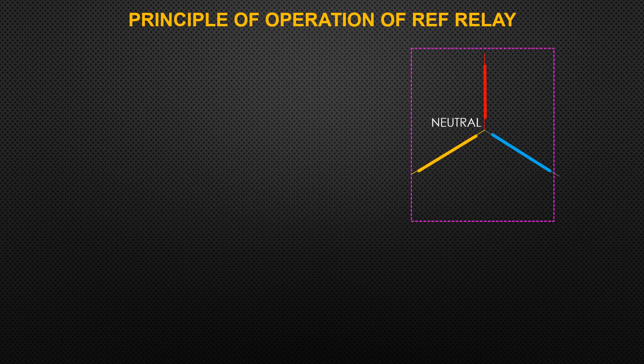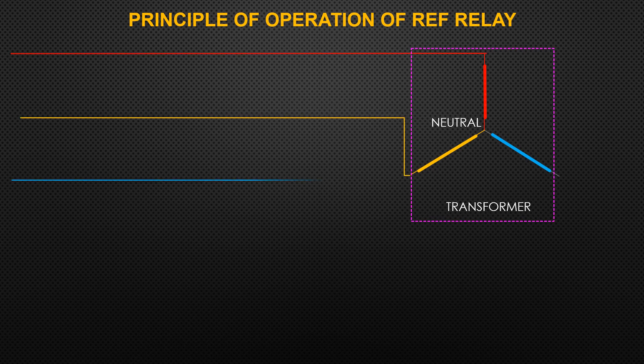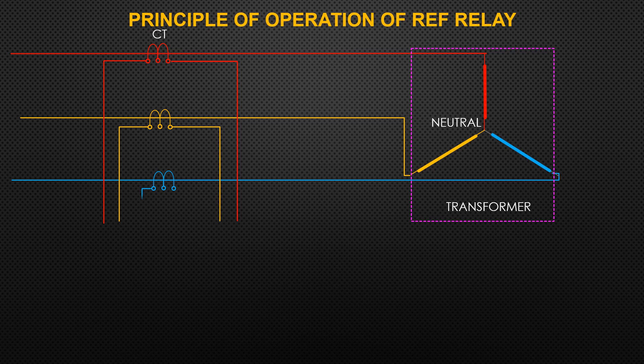Principle of Restricted Earth Fault protection: REF is a sensitive way to protect a zone between two measuring points against earth faults. The CT secondaries are wired to cancel each other's currents during through faults, and to drive all secondary currents to the relay when the fault is inside the protected zone.